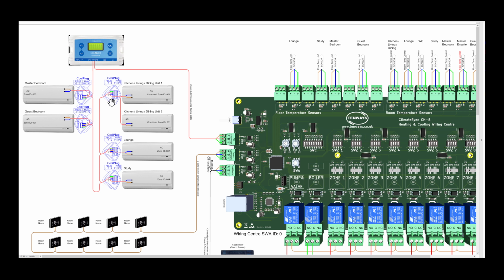Installation of the CoolPlugs can be by the indoor unit, or we can have all the CoolPlugs sitting by the wiring center, and then from each CoolPlug a cable to the indoor unit, as long as it's a CoolPlug that connects to a wired controller and the indoor unit, not a CoolPlug that connects directly on the PCB board of the indoor unit with a small special plug. If it is, then it must be by the indoor unit. If it connects to a wired controller and it's a 2-core cable, or a 3-core sometimes by some brands, then it will be connected either by the indoor unit or by the wiring center.